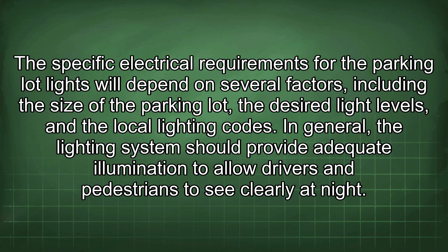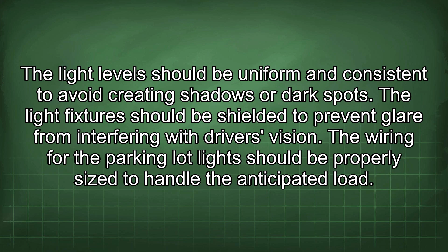The light fixtures should be shielded to prevent glare from interfering with drivers' vision. The wiring for the parking lot lights should be properly sized to handle the anticipated load. The electrical circuit should be protected by overcurrent protection devices, such as circuit breakers or fuses. The light poles should be properly grounded to prevent electrical hazards.